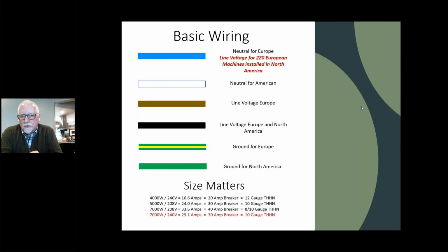They're always hot legs. If you have a machine that's coming in that could be wired in three-phase, with a blue, black, brown, and a ground wire, you can generally operate those machines in single phase simply by putting the brown and the black wires together in the same terminal in the plug.